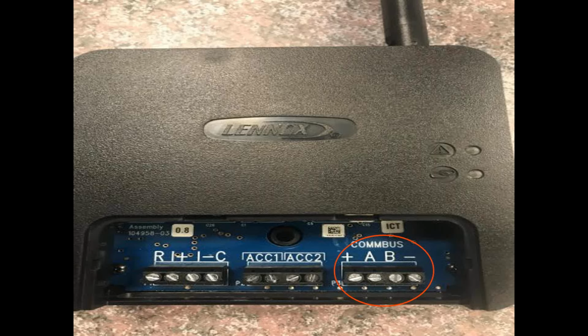But the thing I want to note is that plus and minus are separated, and A and B are in the middle. Okay, so when your team starts wiring this up, or if you have a connection issue or a display issue where it's just not seeing a certain piece of equipment, more than likely, if you pick up an air handler or maybe a condenser and then it doesn't see the display properly, then it's communication. It's going to have some lights blinking on this particular hub and let you know that the display is not communicating. Maybe if you get the air handler to pick up and then the condenser doesn't recognize, then it's usually letting you know that there's some kind of configuration issue with your wiring.